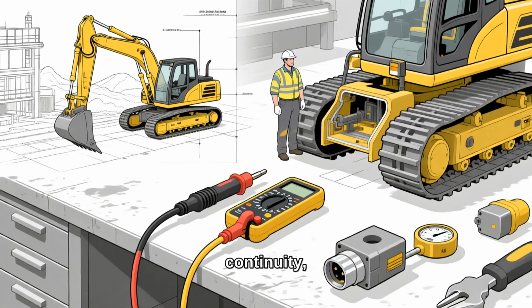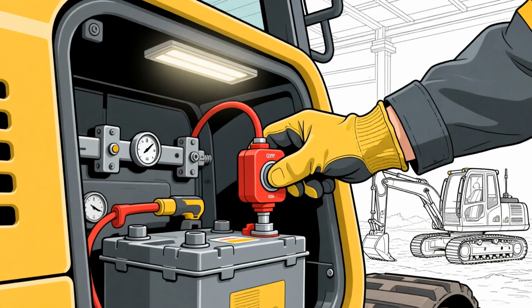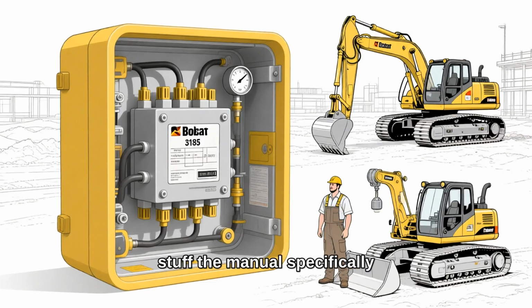Test 5, continuity with the circuit dead and disconnected at both ends, wire to wire, end to end. Power off for that one. Continuity testing a live circuit gives you nonsense and can cost you the meter. And check the cheap stuff the manual specifically points at. Loose spade connectors in the fuse holder.